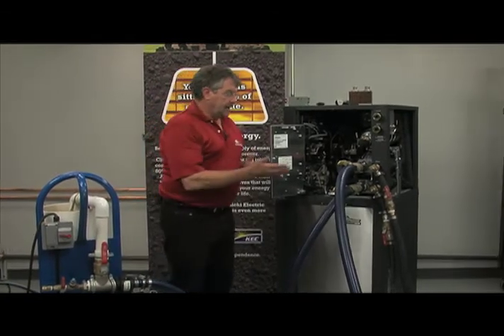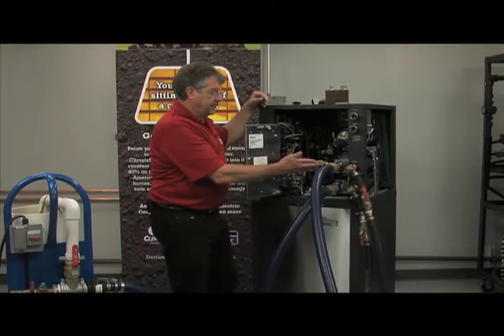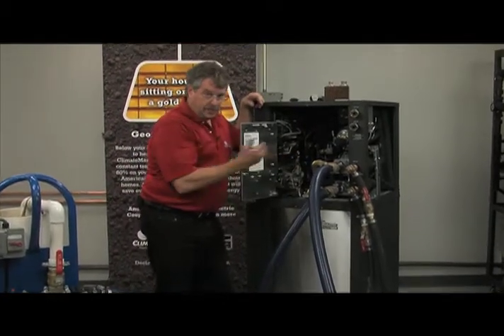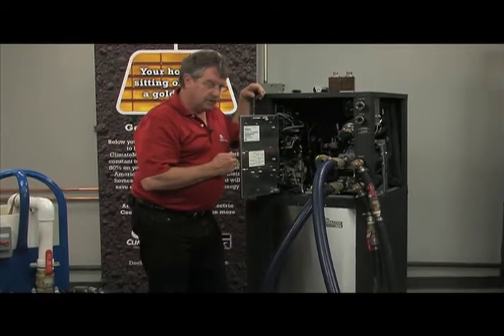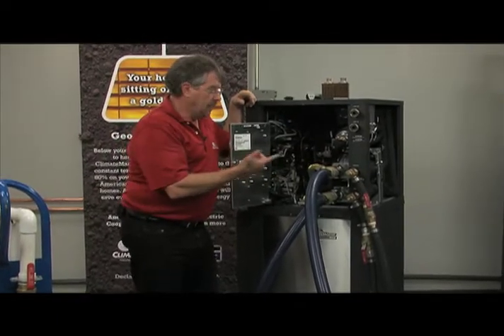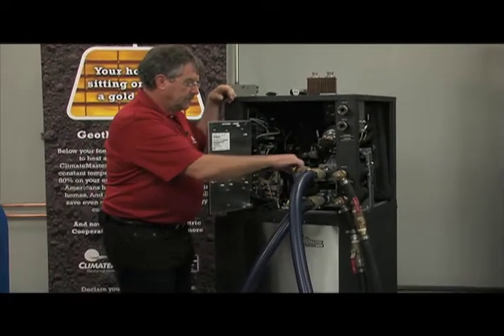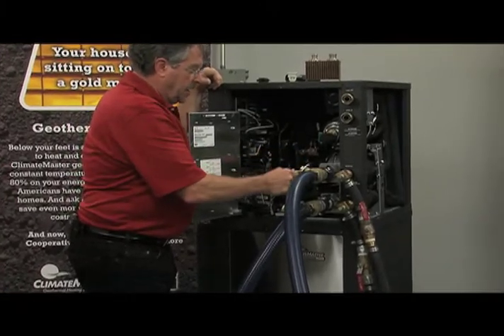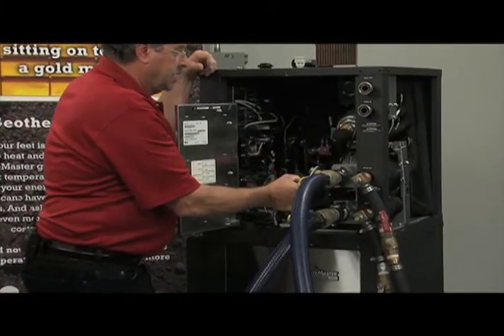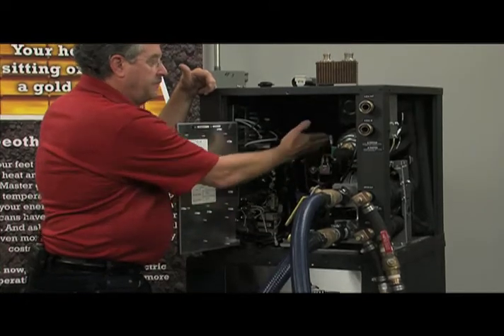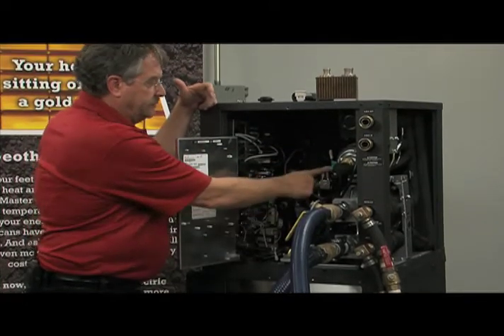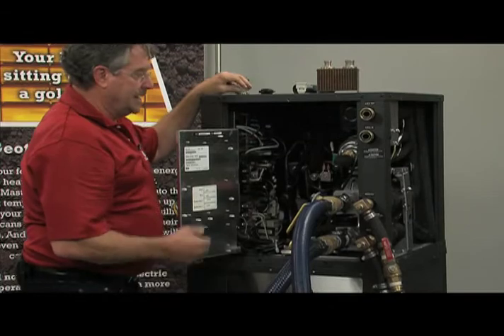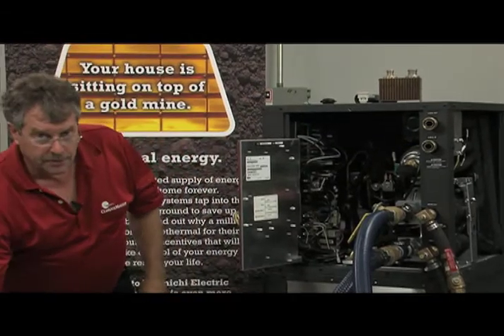So at this point, I'm ready to go ahead and deadhead the unit, but there's still another procedure we need to follow. So in this case, because my flush hoses have shutoff valves at the end, which I highly recommend, it's less messy when you go to pull your hoses from the unit. On that return back out, I'm going to go ahead and shut that off and deadhead that pump, let it pressurize that system. Now I still have my onboard expansion tank. That valve's been closed throughout this entire process, but there's still air in it and I need to burp it.